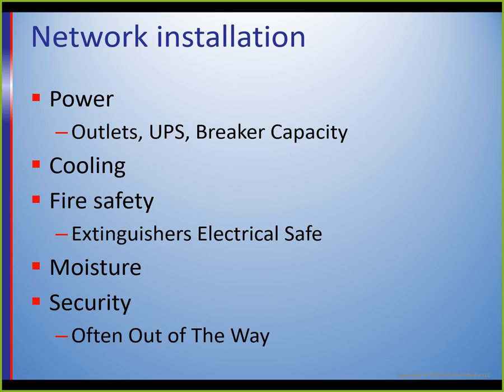Bring in a portable, but do you have an alternate? Bring in a little portable and stick it in there. Where do you exhaust, and what happened with this one? No windows in the room. Where do you exhaust the portable roll-around? What we wound up doing was exhausting it into the overhead so that it could get dissipated to someplace else.